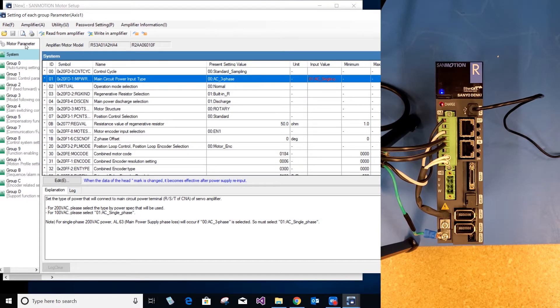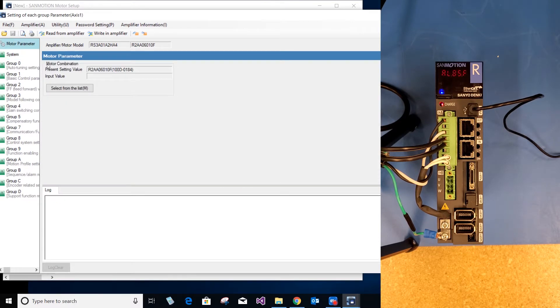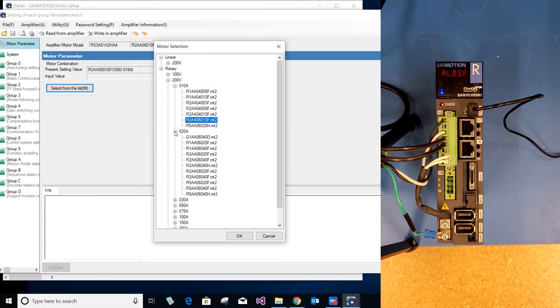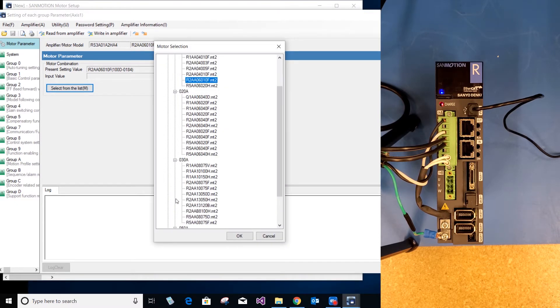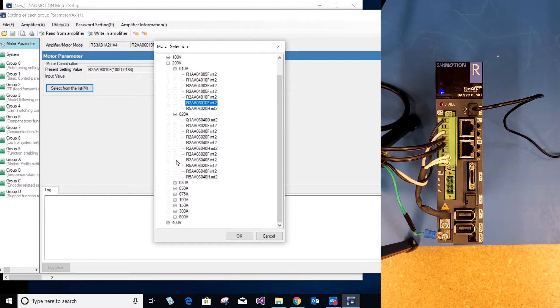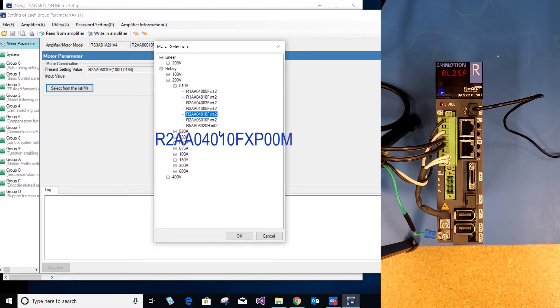Now I will go down to motor parameter, select from the list. Depending on the input voltage and the size of your drive, you have different drop down menus, so you can select the motor you are using. I have a 200 volt 10 amp drive and I am using an R2AA04010F motor. Select OK.